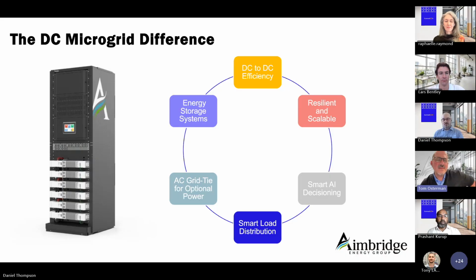I've had those same discussions, even with Trane and EMerge participation in the past, and you're absolutely correct. You can bypass that front end rectification stage and eliminate that conversion loss, which is all about efficiency. If it's not an AC induction motor anymore, but a digital scroll compressor or stepper motor equivalent, that whole infrastructure is DC past the rectifier anyway. So why not go directly in, or have a dual input scheme where you can feed it with AC or high voltage DC and bypass the input rectification side. I don't think it's really hard.